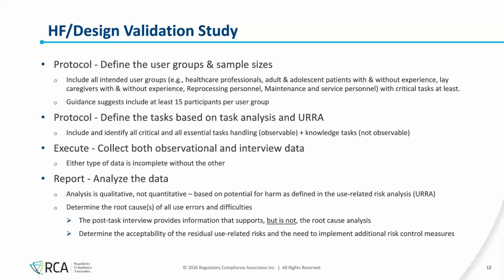So you have a protocol, you define your user groups, your sample sizes, you define the tasks that will be evaluated based on your task analysis from your use specification and the risks identified in the URRA. You go through this exercise within the protocol to ensure you have identified all critical versus essential tasks, and any task that you cannot observe during the study that you're designing, you should include knowledge tasks or knowledge-based questions. So make sure that even if you can't observe them doing it right or not doing it, if it's a critical task, there should be at least a knowledge question or some other sort of evaluation involved for those items as well.